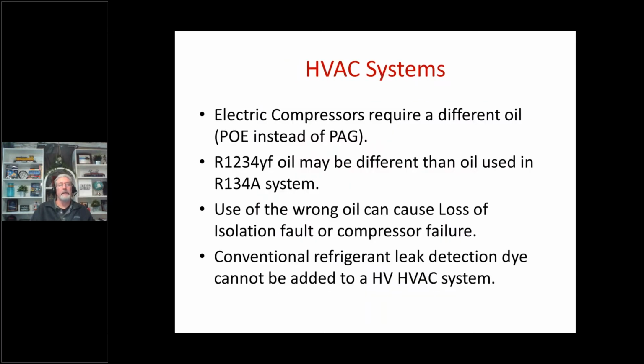So let's talk about HVAC systems. Obviously, if you have an electric compressor, you've got a different oil. In fact, if you have R1234YF, you may have a different oil than, say, 134A. Use the wrong oil, and you may have a loss of isolation or compressor failure.